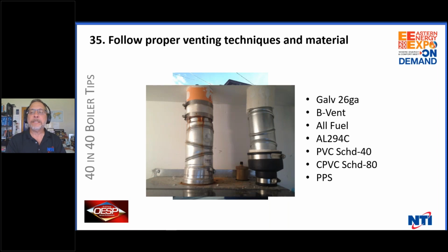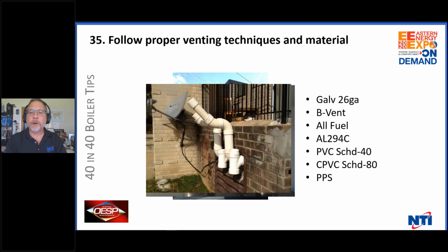Galvanized, because when they ran the PVC and the Schedule 80 CPVC down from above, they didn't line it up with the chimney, so they offset it with a piece of galvanized. I guarantee you that didn't last 6 months. Yeah, now you know why I was there. This is horrible. That's the exhaust sticking up on a 45 and the intake's on a T. You want to have a condensing boiler that's going to suck in water, and you want to have a vent that's going to get hot, or a place for kids to drop down stones like they did on this one.